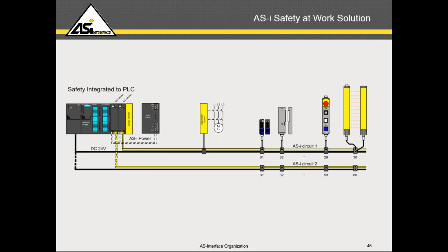When we talk about solutions, we have various ways of completing the entire safety circuit with the higher level PLC that includes the status of all these ASi slave devices back into the main PLC. In this example, we have an integrated ASi solution. The main PLC has the ASi master with safety monitor, which monitors the safety slaves in the field connected on the ASi network. The same network also allows the field safety output cards to trigger the motor contactors. Integrated I/O mapping to the main PLC allows diagnostics information to flow to the HMI for the status of each slave device.